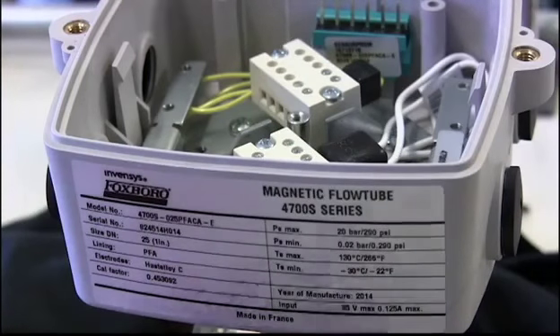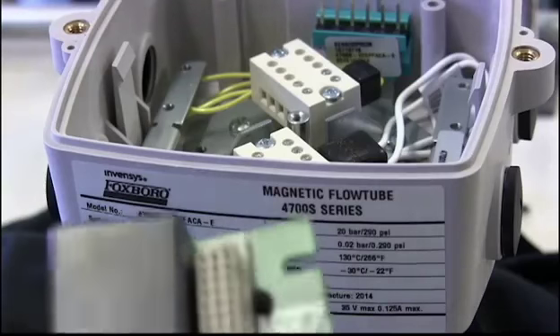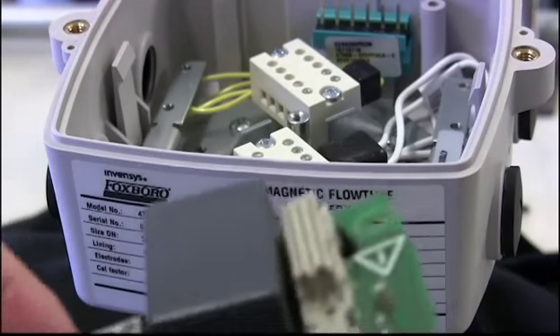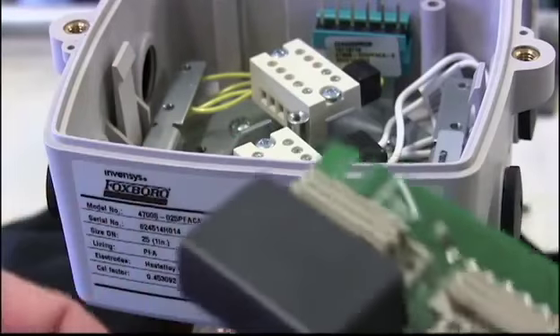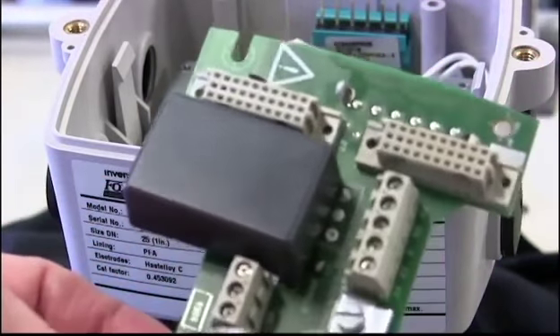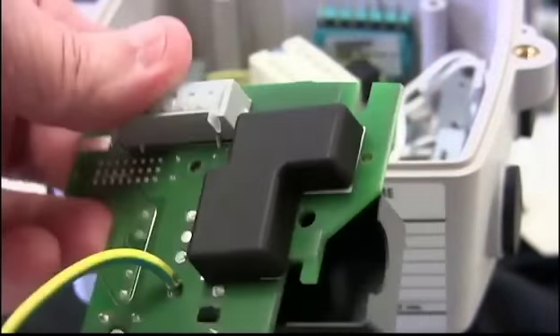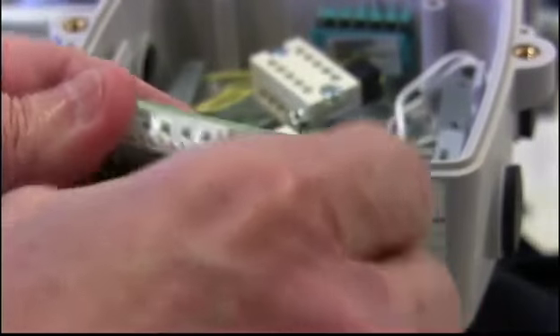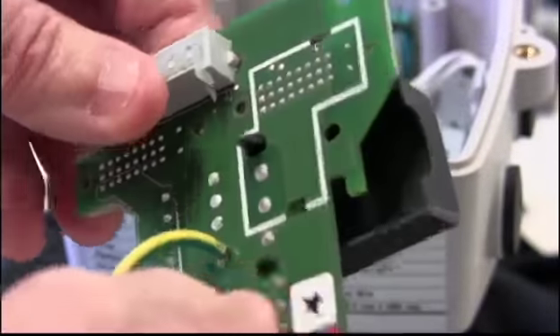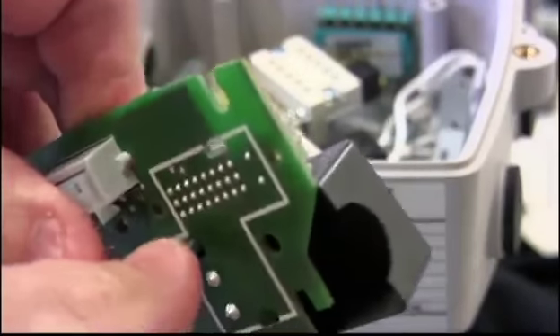Now the first thing you want to do is remove the connector board from its protective bag, and you notice there are a couple of shrouds here. There's one on the top. Can't be removed until you actually remove the one on the bottom. So once you take that out, it just snaps out. It exposes the pins that are holding the shroud on the top. So just depress those in, that one comes off, really nice. Now it exposes all the terminals, so we can start wiring this thing up.